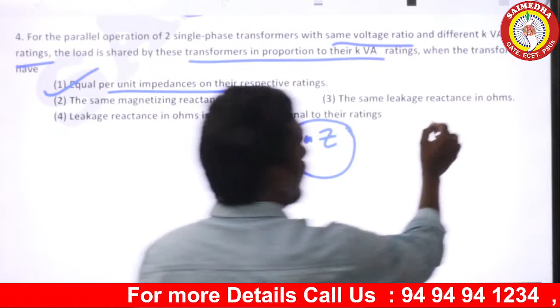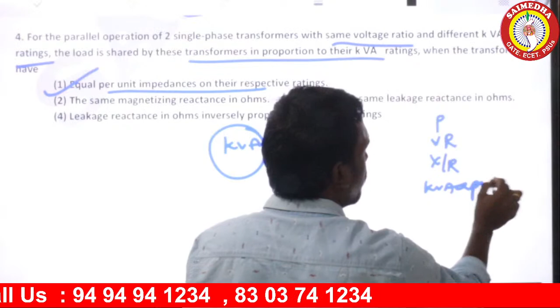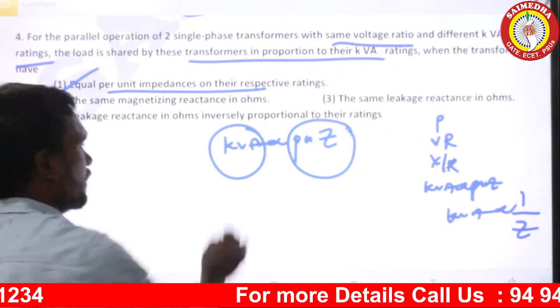Generally in single phase transformers, what are the conditions? The polarity should be same, voltage ratio should be same, X by R ratio should be same, as well as the KVA directly proportional to per unit impedance, or of course KVA inversely proportional to impedance. Okay, so you need to remember those things. Next one.